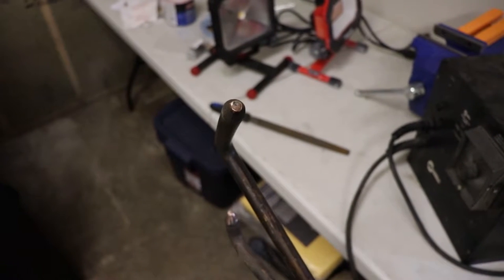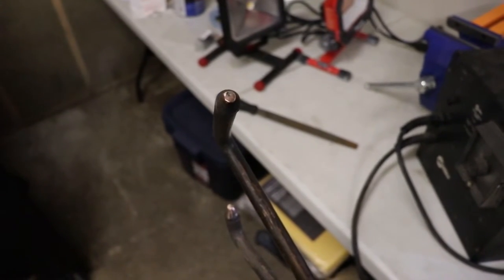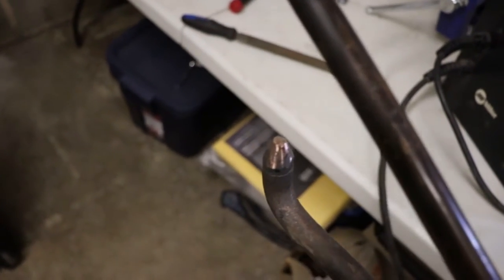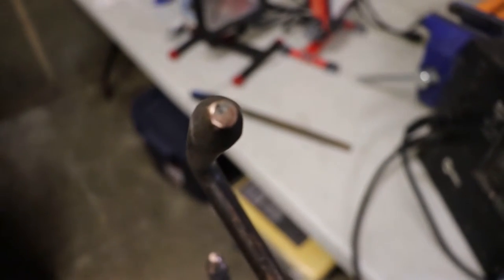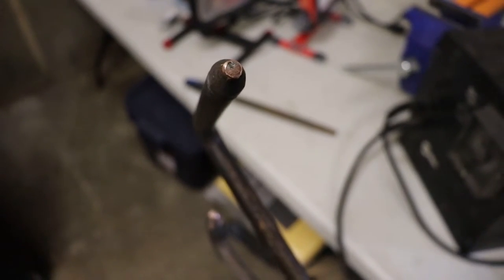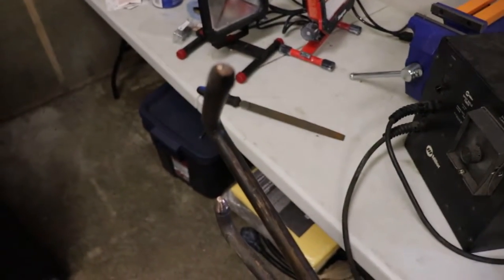All right, so there's a bit of a crater in the tips of the tongs. You can actually replace these, but I'm just gonna file it down and make it work. And it was transferring onto the bottom one. So obviously if you're not getting good contact, it's gonna burn away the copper. It's gonna get away on you fairly quick. So you want to maintain this on a regular basis.